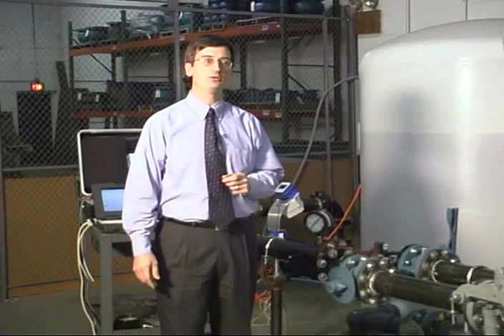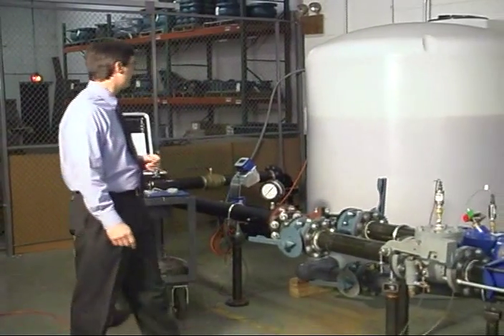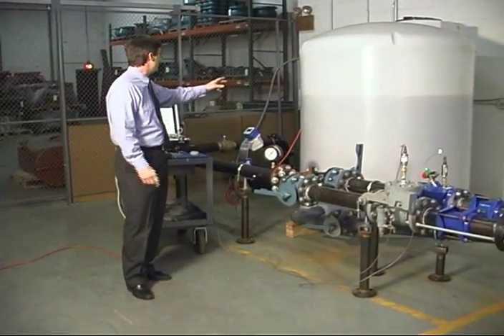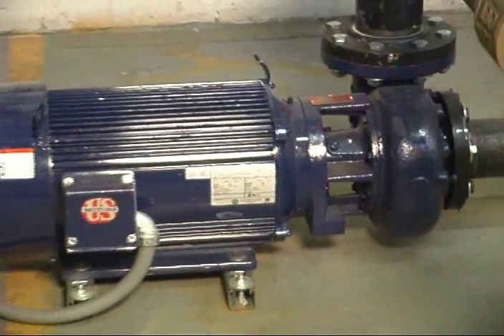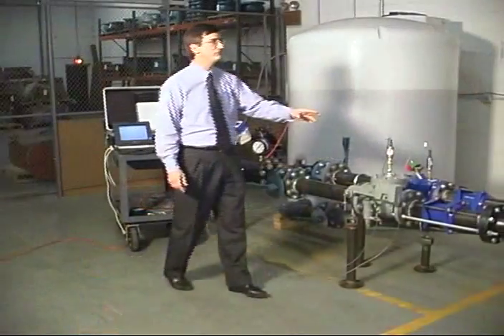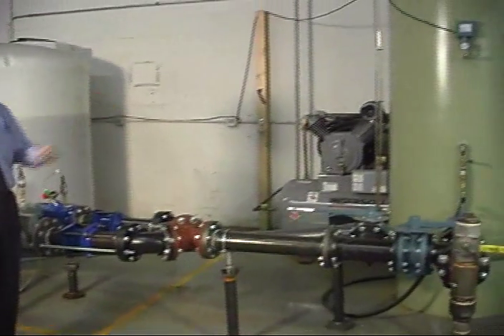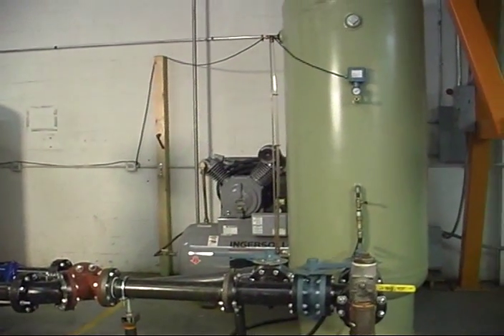First, I'd like to show you a little bit about the flow loop that we have in our lab. It's a water flow loop consisting of a 10,000 gallon tank and a 20 horsepower water pump that sends water through these test lines into a 400 gallon air over water tank, which we can pressurize up to 100 psi.